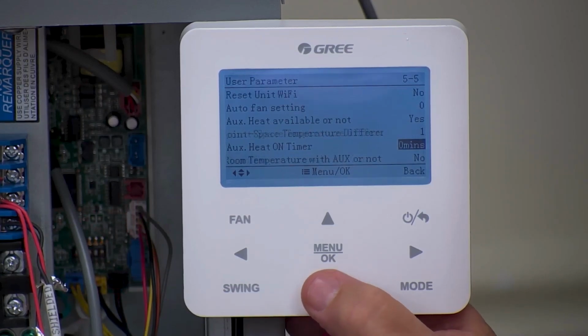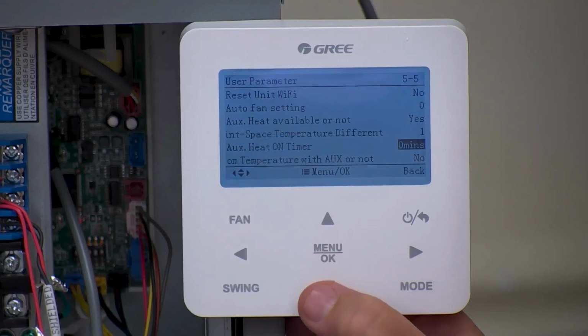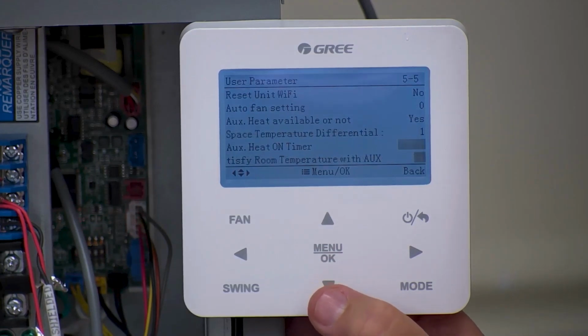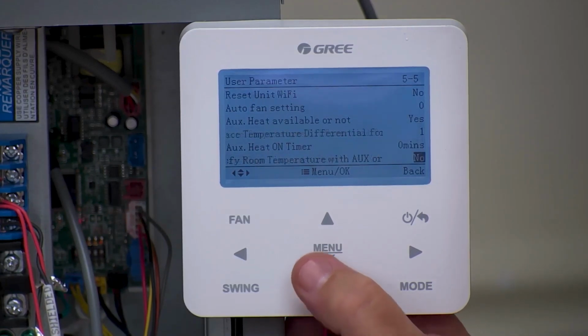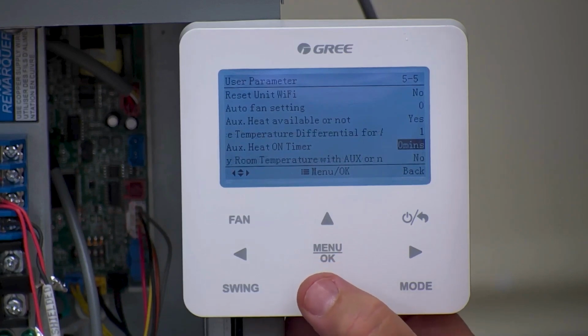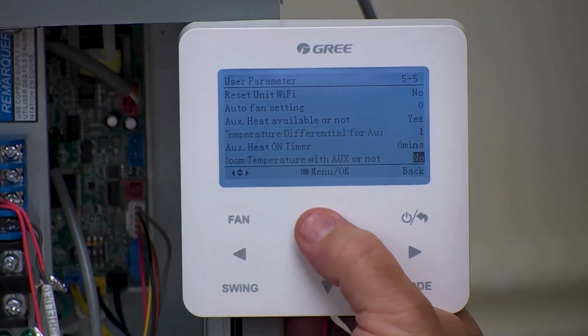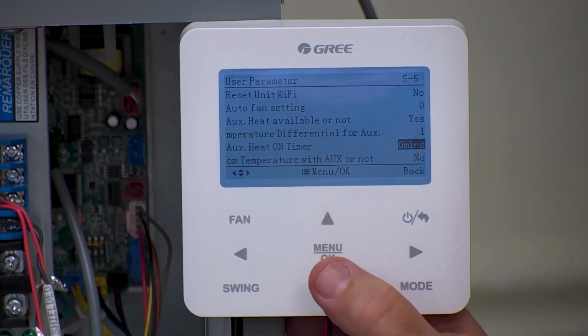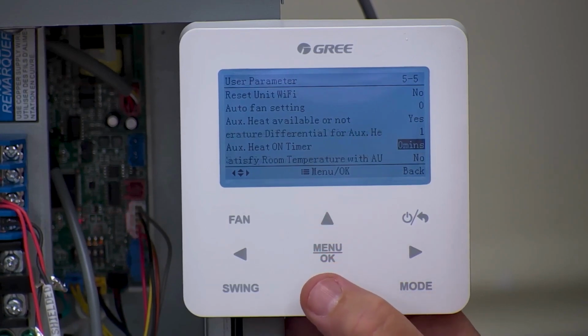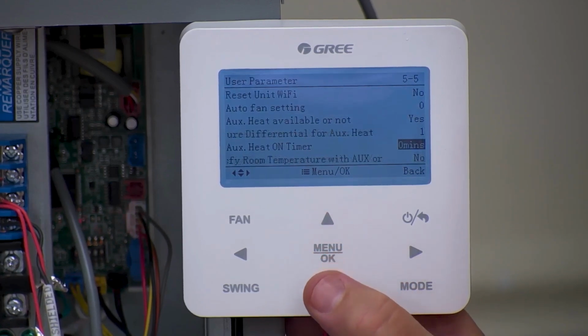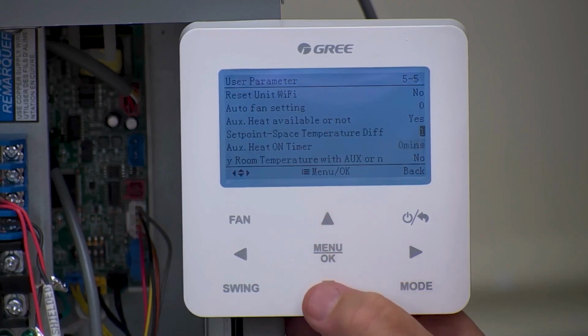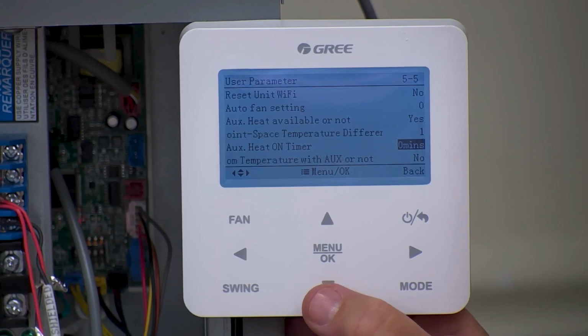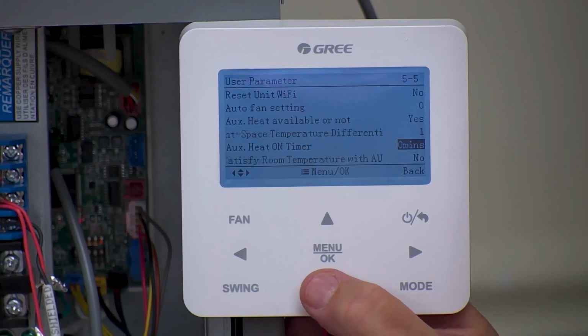So let's say you set it at 15 minutes. So even though it called for auxiliary heat because we got a 1 degree differential because it was 60 degrees in the house, we set it at 70. We gave it a 10 degree differential. It's not going to bring on the electric heat for at least 15 minutes. It's got to elapse that timer before the auxiliary heat kicks in. That's what that means. Or you can just have it as simply as 0 minutes, and every time you're within 1 degree of your set point, if you're below that, then you're going to bring on the electric heat.